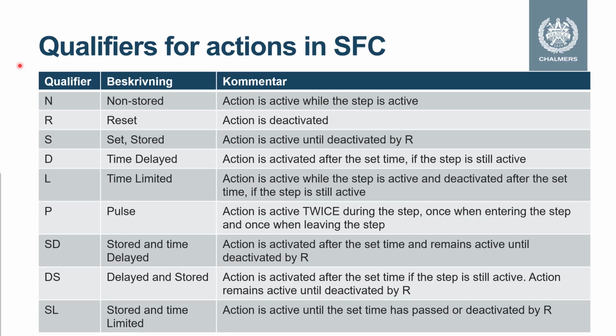We have a few more qualifiers we can use. N for non-stored. That means that the action is active as long as the program is in that step. We can use an S, that is stored, which means that the action is activated when the program enters the step, and then it remains active when the program leaves the step until it gets to the qualifier R in another step. Then the action is reset in that step.